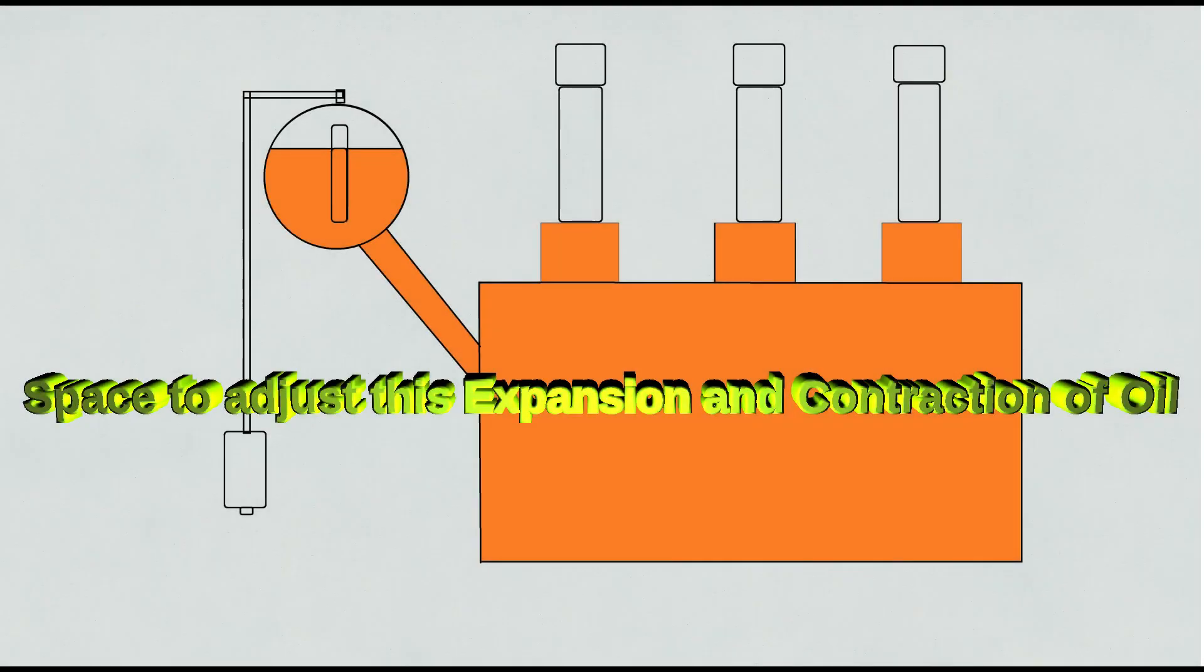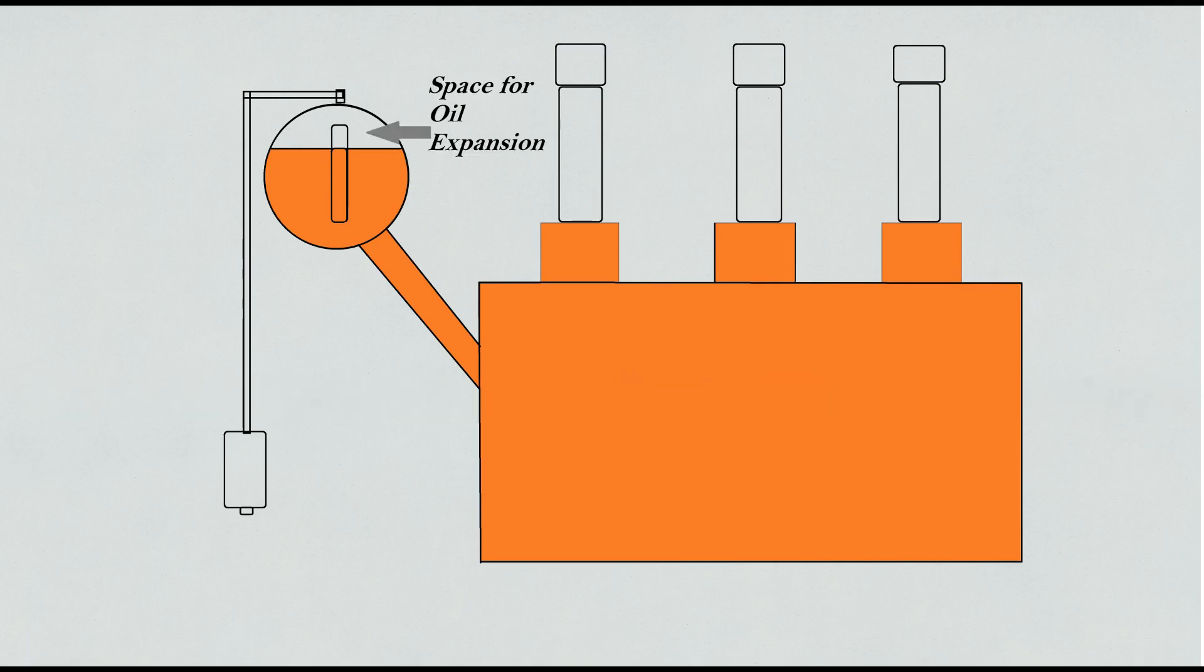Hence an outlet and space is required to adjust this expansion and contraction of oil. So to accommodate expansion, space is provided in the oil conservator tank, and an outlet is provided through the breather.